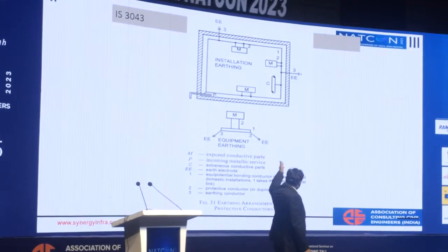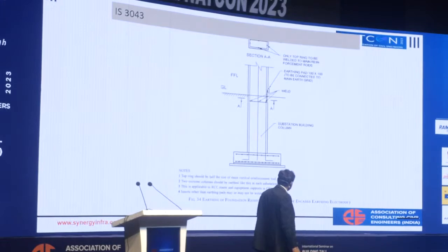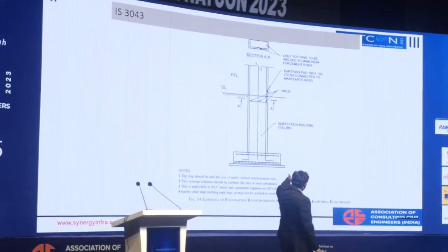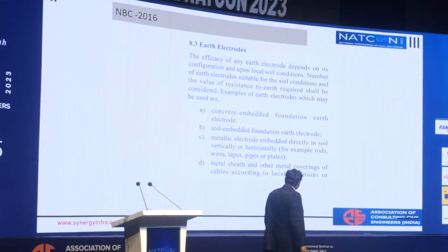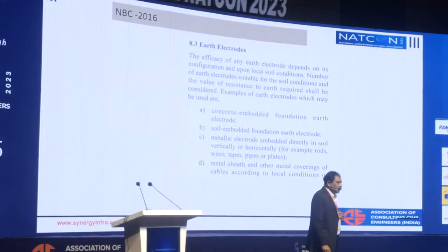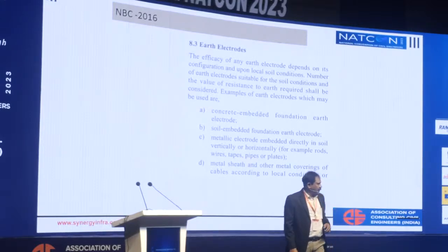And here also, this is a ring main basically, which is supposed to be provided in any substation. And this is the earthing of foundation reinforcement. Whatever your column is, you can see there is a ring earthing pad which is specified, which is supposed to be connected to the earthing grid. So this is what is given in all our electrical codes. And it also says in the NBC, National Building Code 2016, the concrete embedded foundation earth electrode is one of the most important. That is the first thing.